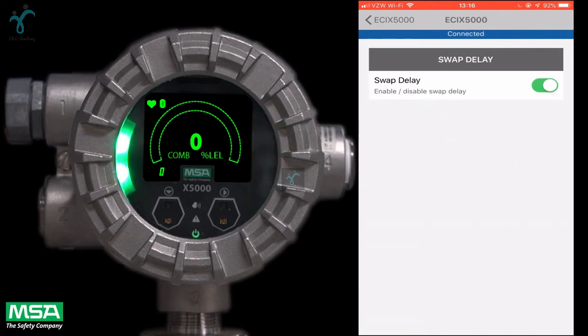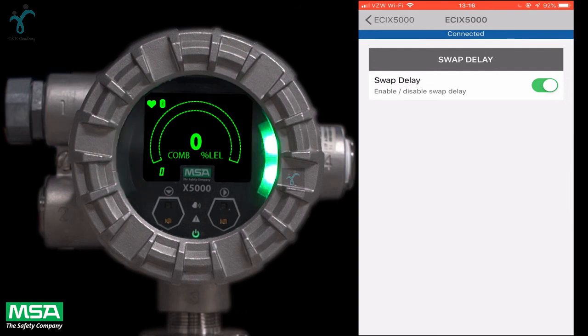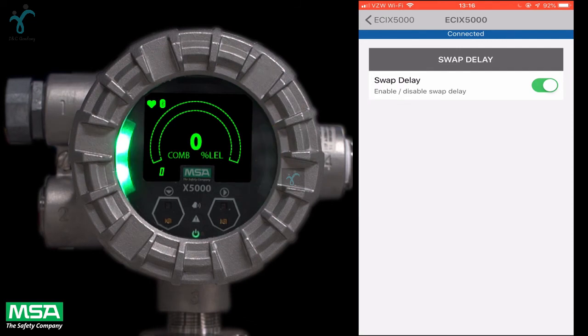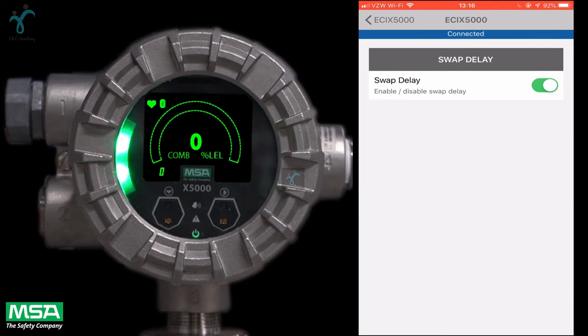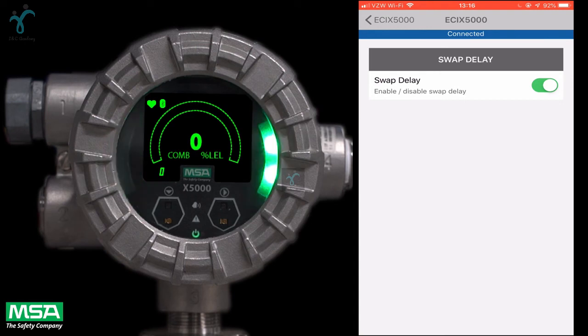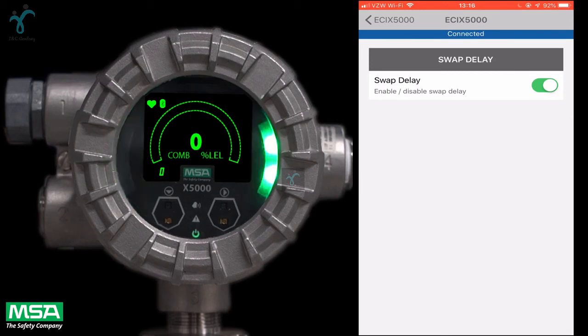Swap delay allows the user a brief window to change an XCell sensor without the device going into a fault condition. Once a sensor is disconnected from the transmitter, the user will have 2 minutes to reconnect a sensor. If a sensor is not reconnected after the 2-minute window, the Ultima X5000 will enter a sensor-missing fault condition.